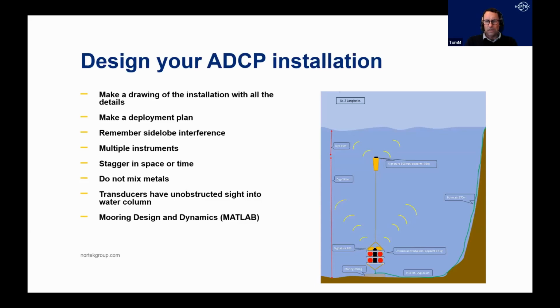Another thing we see is that people are losing instruments, unfortunately, and a lot of things come into us attached to a frame. For instance, we see people mixing metals, for instance stainless steel against shackles that are galvanized, and this will corrode away. So please do remember, never mix metals. And if you have to mix metals, be sure to isolate them from each other by using bushings, nylon bushings and things like that. Another problem we also see is that transducers are hitting something in the water. So make sure to have an unobscured sight into the water column.